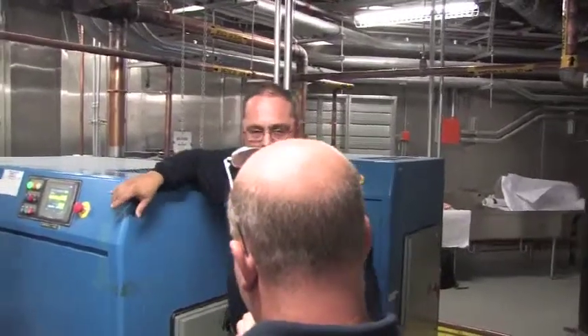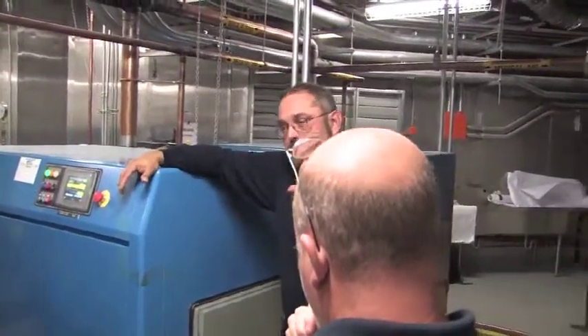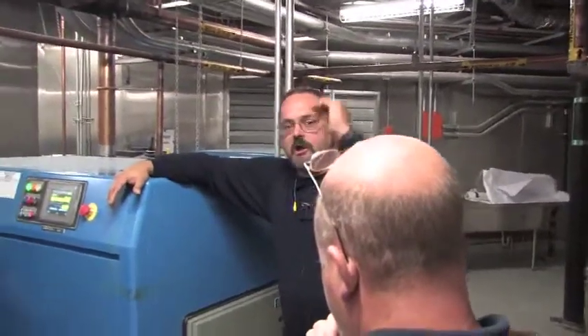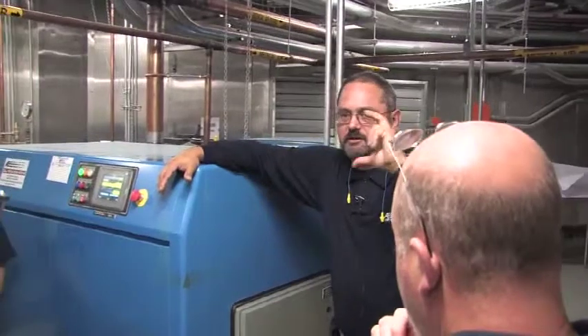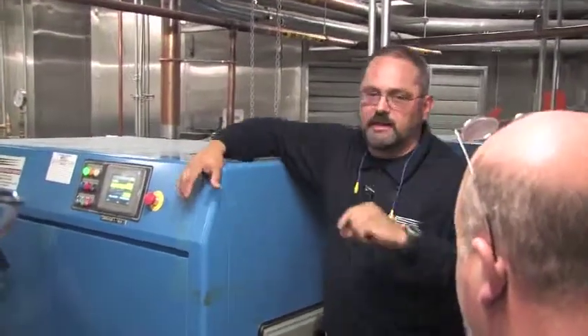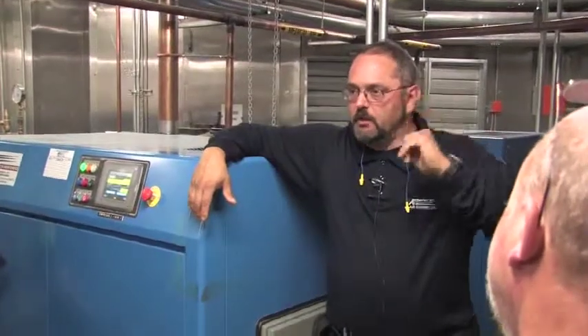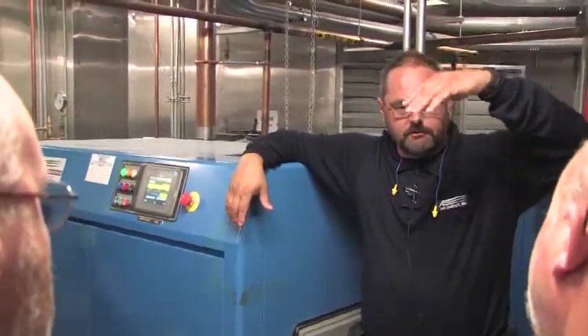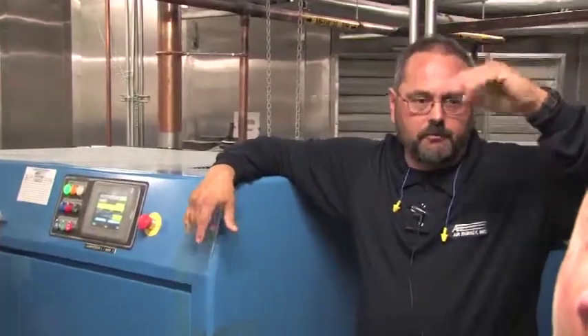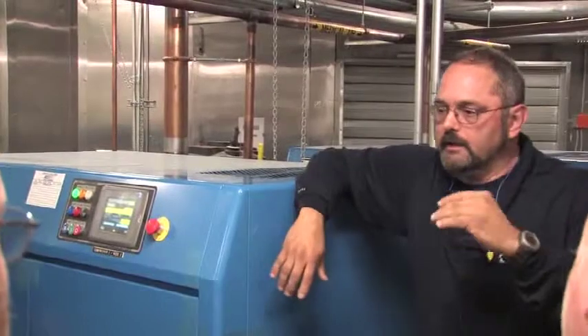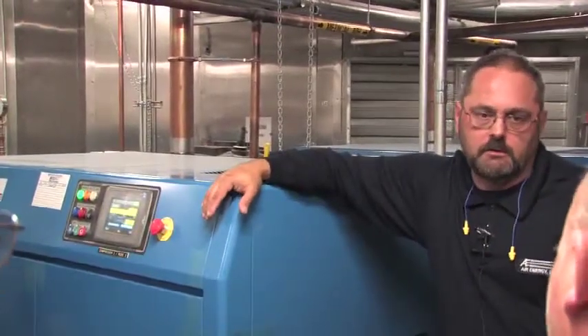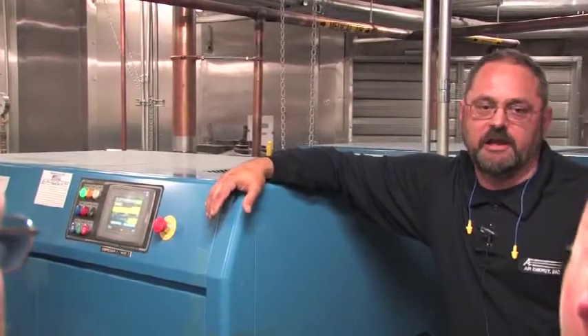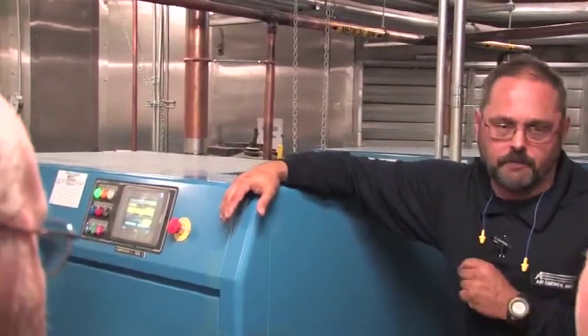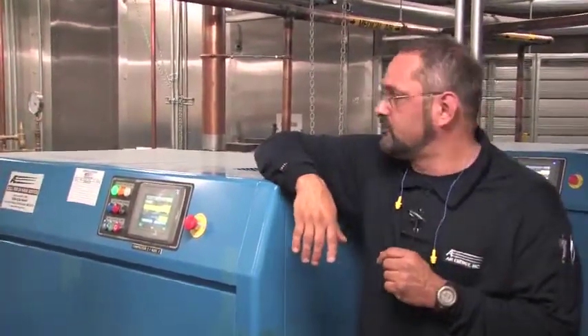The way the sequencer works now is you set an ultra high, and you set a band where you actually want the system to run. For example, right now this one is set 90 to 100 with a high of 110. So if it overshoots, it'll allow it to go to 110 and then it will unload everything. And it will go as low as 80. If the pressure suddenly spikes and drops to 80, the sequencer will start all three of them. Now the other thing the sequencer does, and right now it's evident that sometimes you'd think only one of them would load up if something happened.